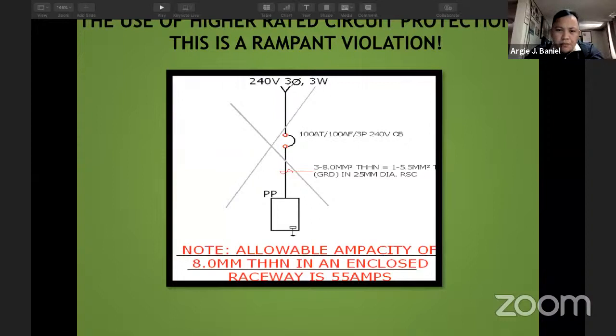The main design and function of the breaker is to protect the branch circuit wirings and its connected appliances, but it cannot protect against overloading because its rating is set too high.